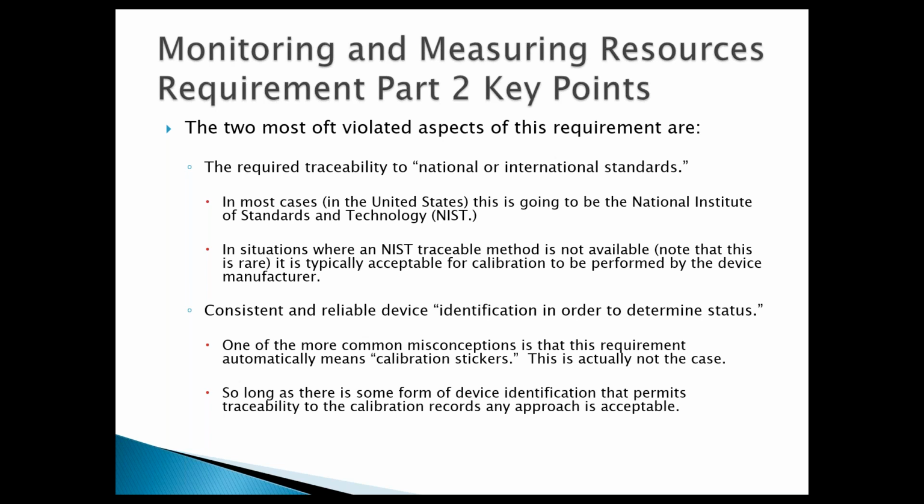And they issue these national standards and verify these national standards, and it spreads out by a series of master laboratories and sub-laboratories and so forth. So what we're looking for when we look over your calibration records, we're looking for that NIST code. Is the calibration that was done for this device traceable to a NIST reference number?